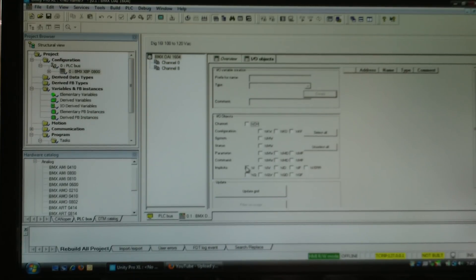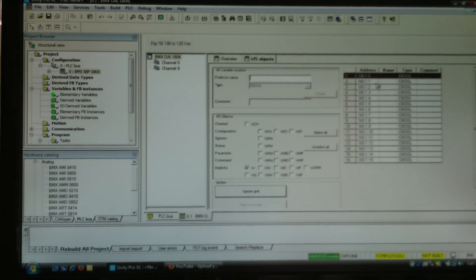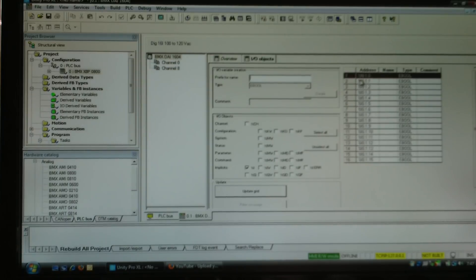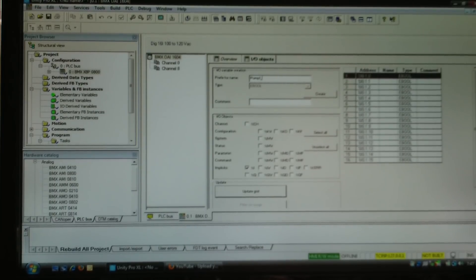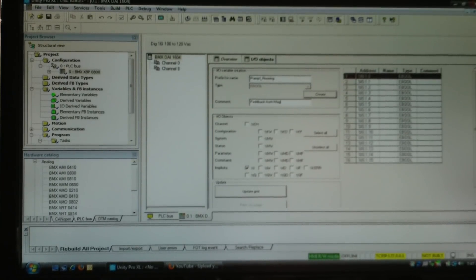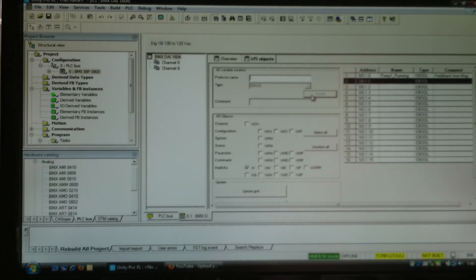I'm going to use %i because that's my actual physical input channel. I'll update the grid and it lists all the addresses. You see it's the IEC style address because Unity is an IEC style package. I have %i 0.1.0 — %i for physical input, 0 is the rack, 1 is the slot, and 0 is the point on the card. It's IEC based and the M340 is a 0-based processor. I can come over to the name field, type in 'pump1running', add a comment like 'feedback', and click Create — it creates a tag name and comment for that point.